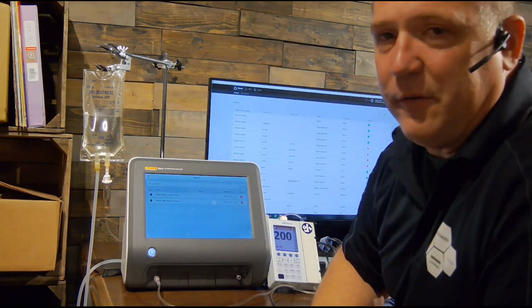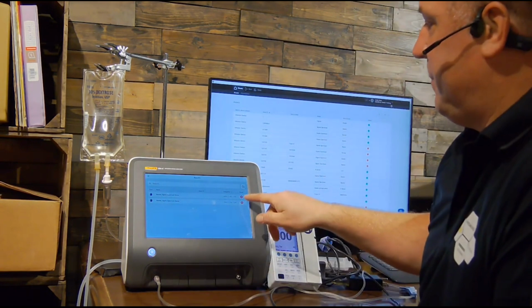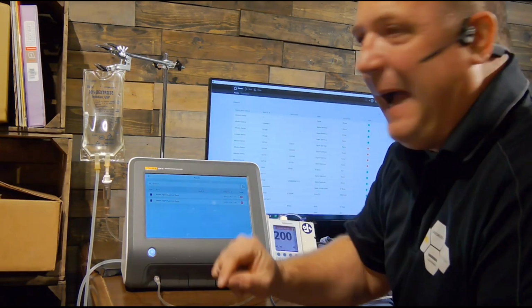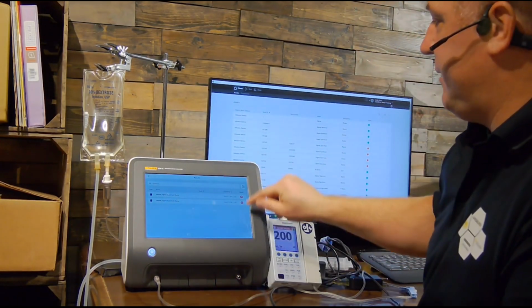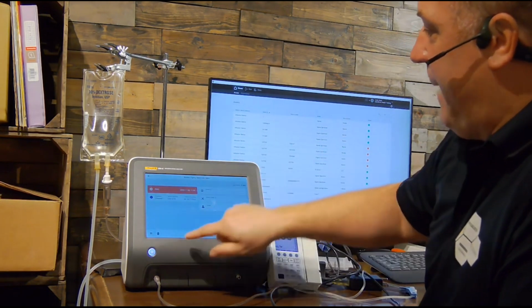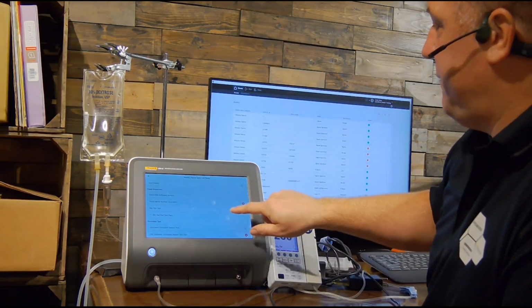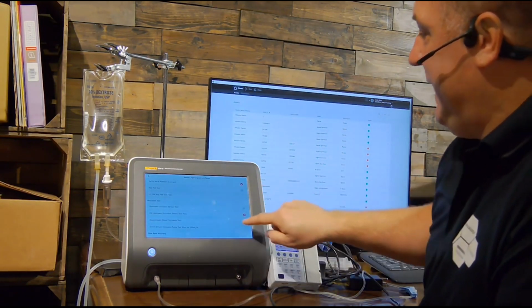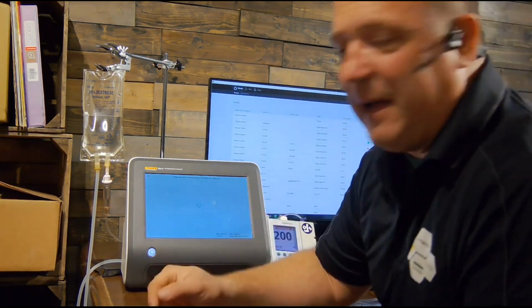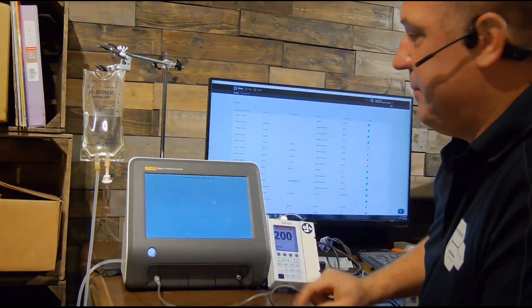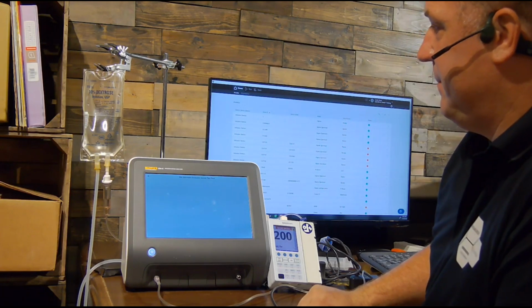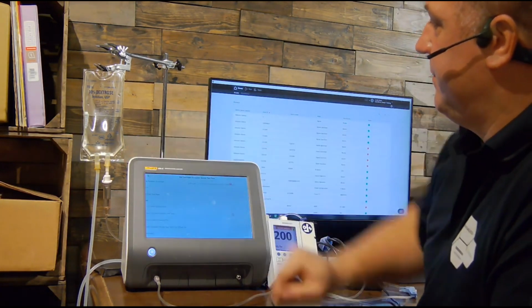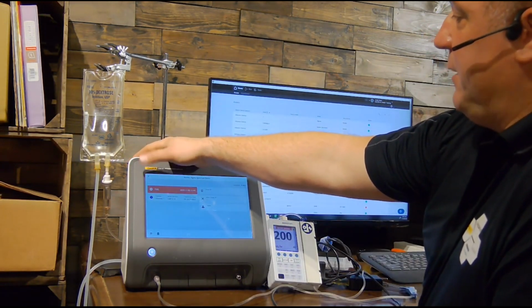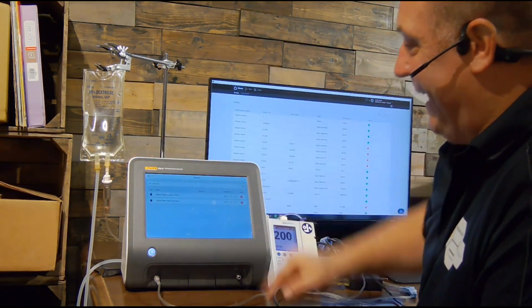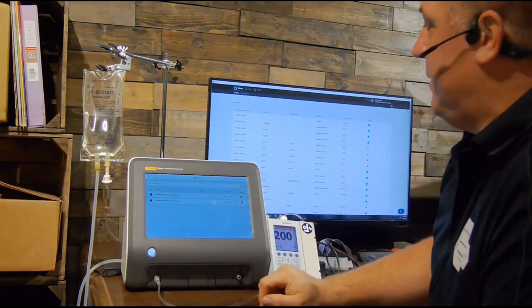So here's every test I've run with the IDA-6. You can see I've been doing demos, and I've failed the procedures, so I have red X's. If I passed it, I'd have a green light here, and I could go into these and see what happened. I can go down here to my notes, and I can see, oh, it failed right here, and it failed here. I can't change anything on these screens now because I already finalized it, but I can see what happened without going back to my PC. It's right here. Again, just touch on it, and there's why it failed. So obviously, if you're doing a whole bunch of IV pumps, this list is going to be quite extensive. I've only done 2 since last time I synced, so you're only seeing 2 today.